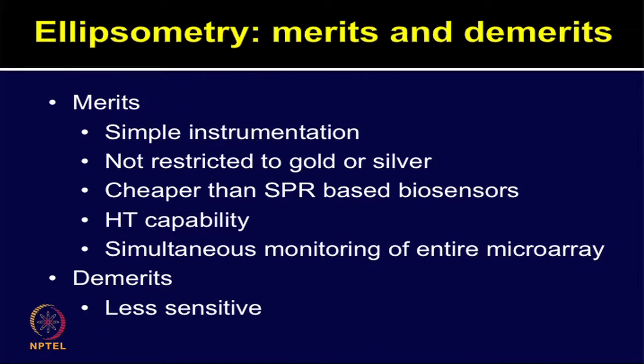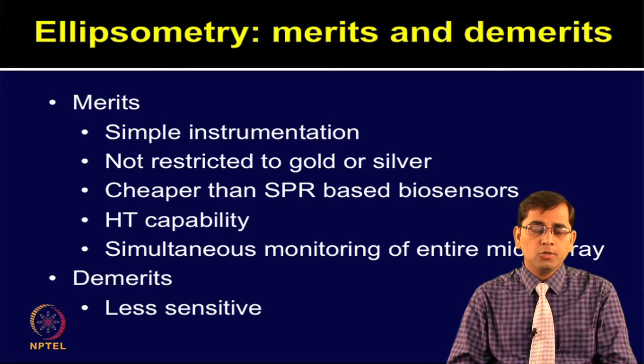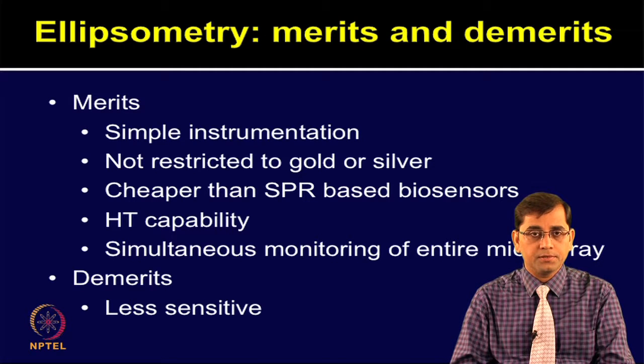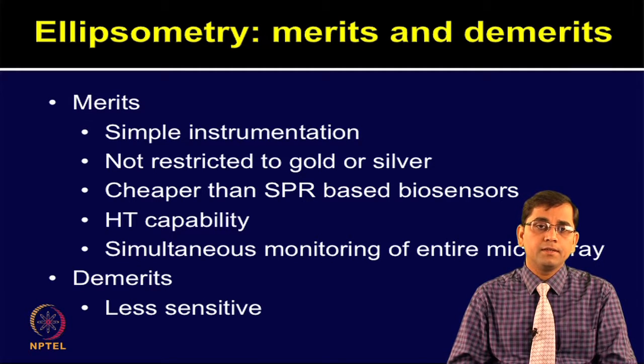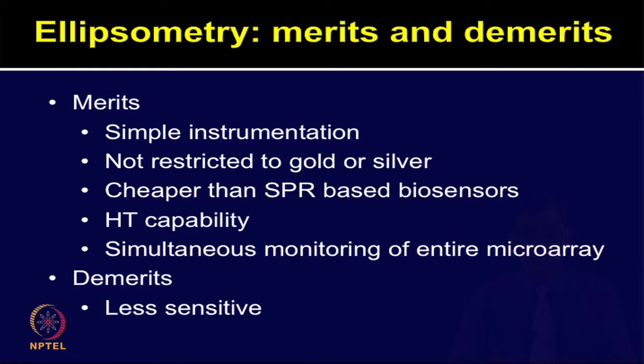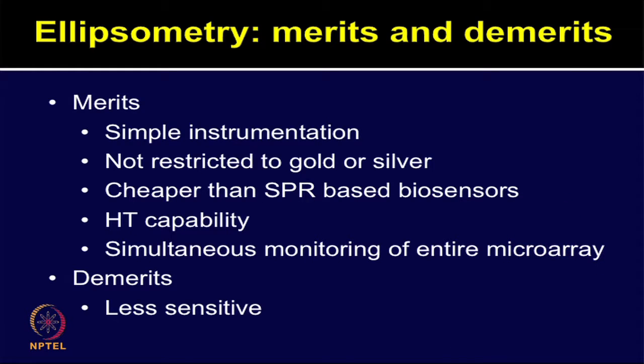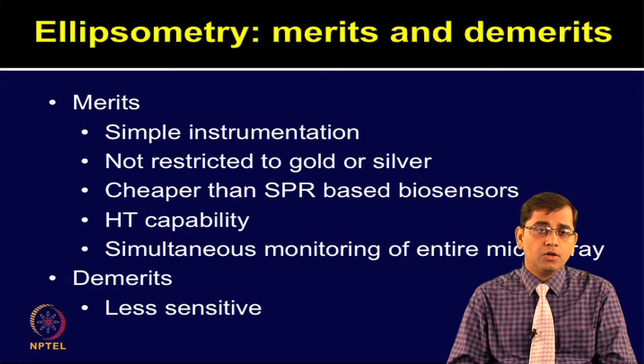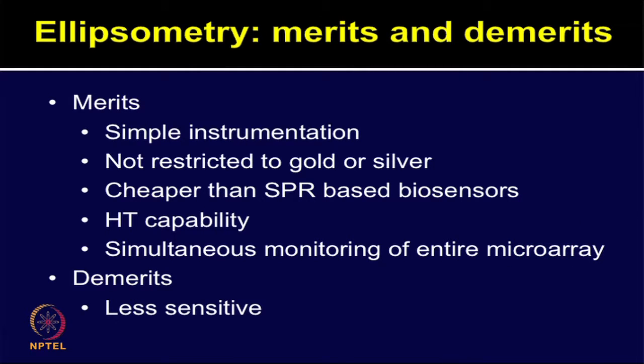Ellipsometry-based approaches have many merits. The instrumentation is very simple, unlike SPR-based instrumentation. It is not restricted to gold or silver surfaces. It is more economical than previously discussed SPR-based techniques, and it provides high throughput capability with simultaneous measurement of an entire microarray. The demerit of the approach is its sensitivity — it is less sensitive than SPR or SPR imaging-based techniques.